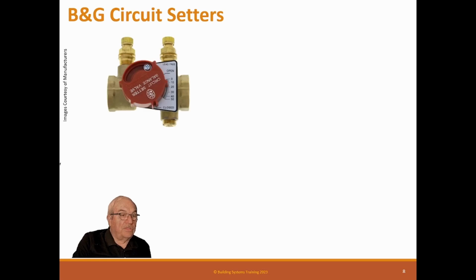They were the first ones to produce this valve that I'm aware of. And this is a typical valve. They make a whole bunch of different kinds and all different sizes. And they have a little gauge out here that tells you what the setting is of the valve, and it's lockable. So you can turn this thing and then lock that screw, and it locks it in place. So someone can't inadvertently try to use it as a shut-off valve.